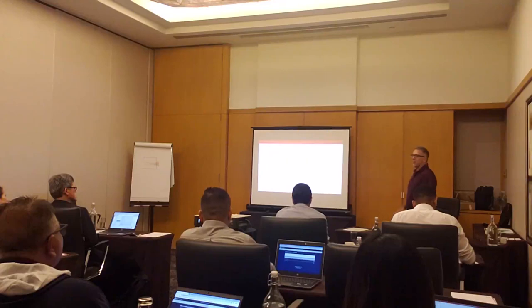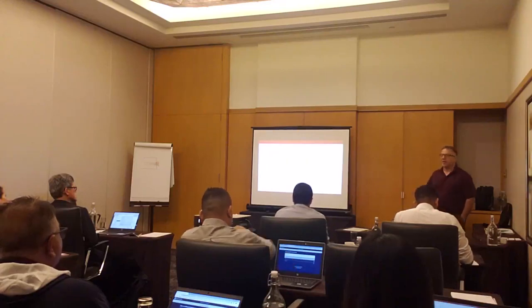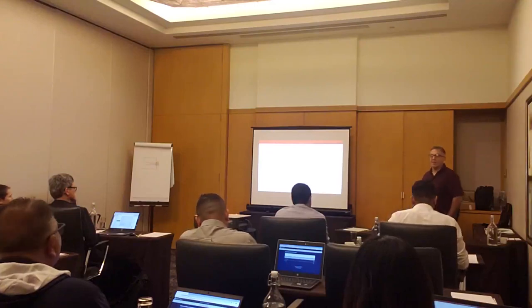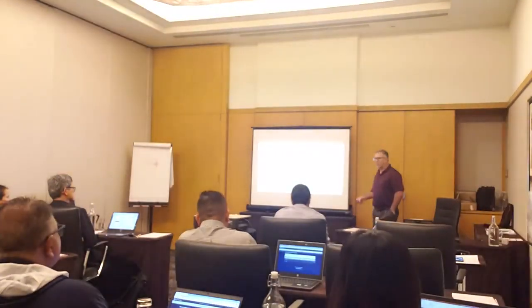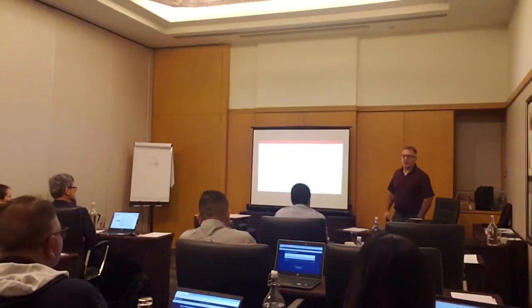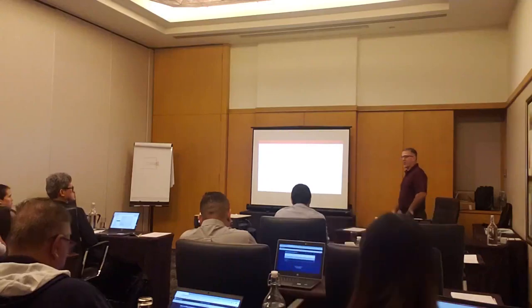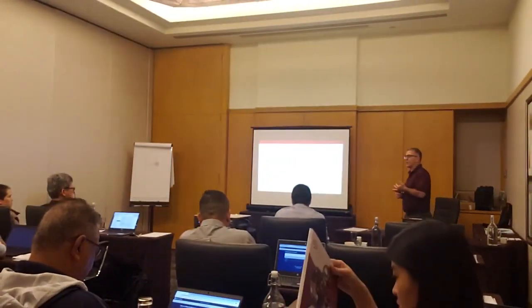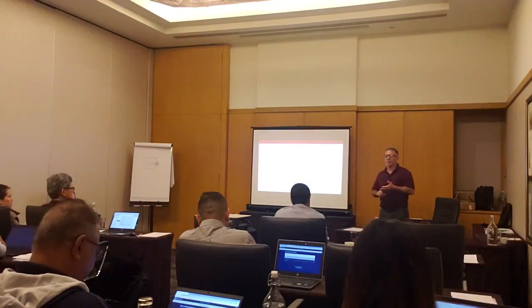Remember, the NFPA standards are minimums. So that doesn't mean that you can't run it longer if you feel the need to do that. And when you look at a procedure for your company, it could be that it might say 30 minutes for both of those. So it just depends. I know that when you send out maintenance personnel to do these, they like to do the electric pumps a lot better than the diesel pumps because they're standing there for 30 minutes while it runs. There's some things that they should be doing during that time. They're looking for heat, looking for vibrations, and monitoring the RPMs and the pressure to make sure that they maintain those minimums.